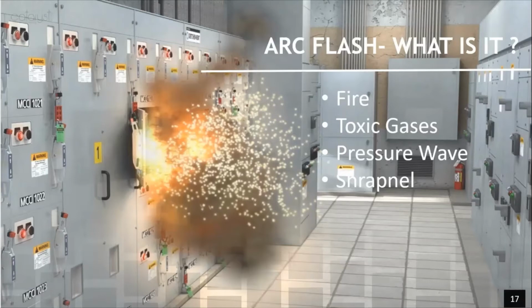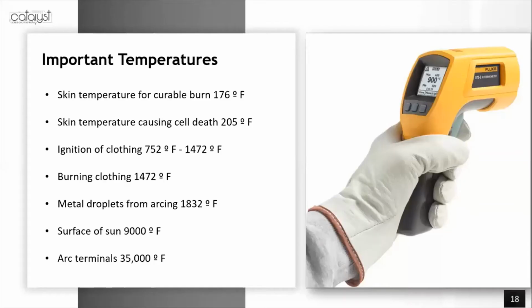and that could cause incurable lung damage. The other thing I'm going to lead into is the pressure wave. When copper flashes to a vapor, it expands 67,000 times, as opposed to water at about 1,600. So it's an explosion. An arc fault generates a tremendous amount of heat, and that expansion of the air can cause barotrauma. It can cause all kinds of things to happen. You could have enough of a concussion that it could throw you backwards. You could be impaled by something else. Another one is shrapnel, because we mentioned the arc in a box, so you could get pieces of shrapnel coming at you. So that's kind of what happens when the flash occurs, depending on the extent.